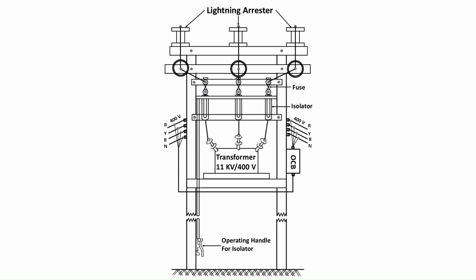Here you can see the layout of a pole mounted substation. The transformer and other equipment are mounted on an H-type pole structure. The 11 kV line is connected to the step-down transformer through an isolator and fuse. The lightning arresters are installed on the HT side to protect the substation from lightning strokes. The transformer steps down the voltage from 11 kV to 400 volt 3-phase 4-wire supply. The voltage between any two lines is 400 volt, whereas the voltage between any line and neutral is 230 volts.